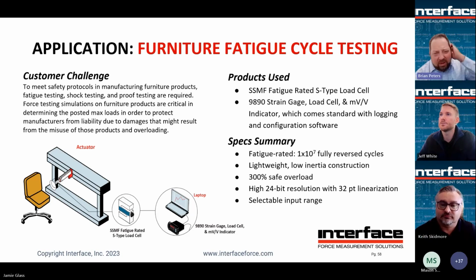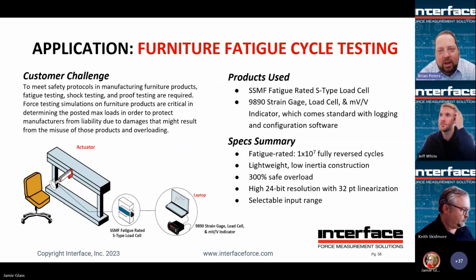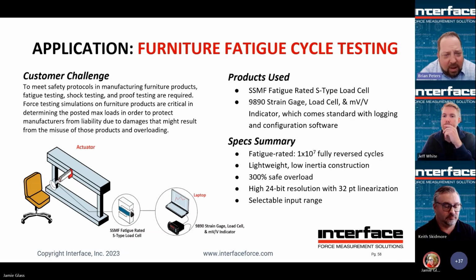So here's a high cycle fatigue test application. In this case, it was furniture testing. Again, most of you probably know how almost every single thing out there gets tested. In this case, the choice was an SSMF. It's a fatigue-rated S cell, well suited for high cycle testing. In addition to that, it's low weight, so you're not adding a lot of inertial element to your cycle testing. Good safe overload too, 300% safe overload.